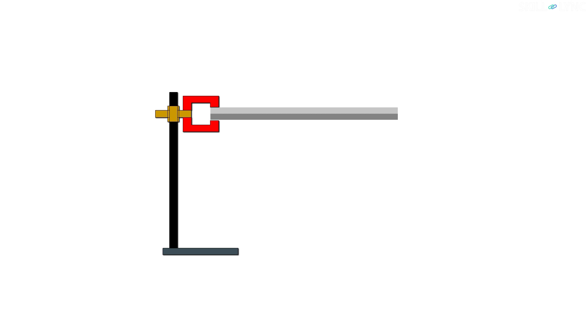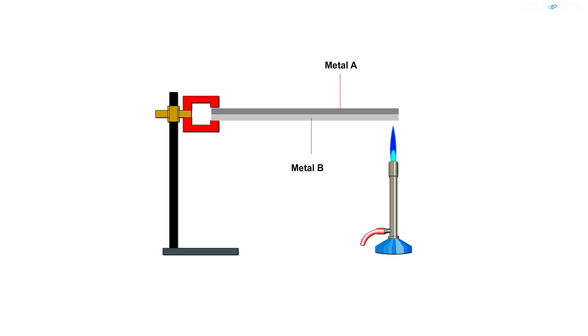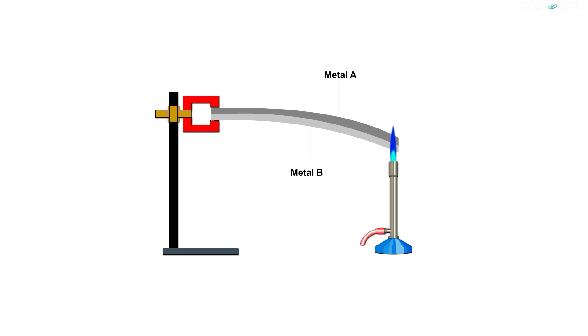Let's start with the bimetallic sensor. As the name suggests, this sensor consists of two metals — two metal strips having different coefficients of expansion. The metal having a higher coefficient of expansion is present on the outer side, while the metal having a lower coefficient of expansion is present on the inner side. When the metal is subjected to temperature change, it bends into a curve. Since the two metals are joined together and possess different values of thermal expansion, the metal with the higher coefficient tends to expand more. The two metals being attached to each other prevents the one with the higher coefficient from expanding faster, thus forcing the two metals to bend.